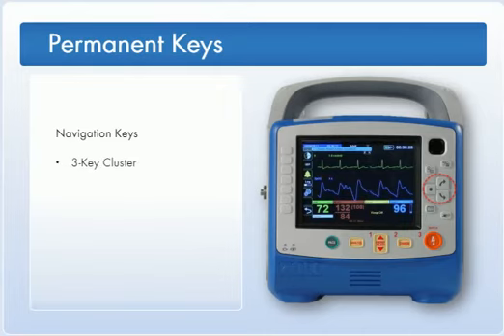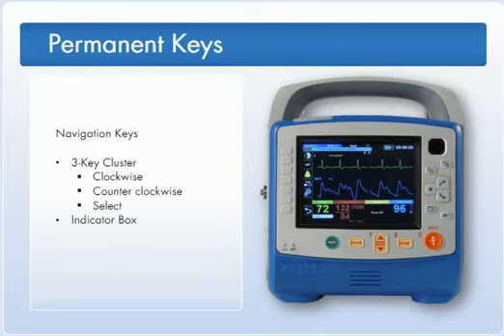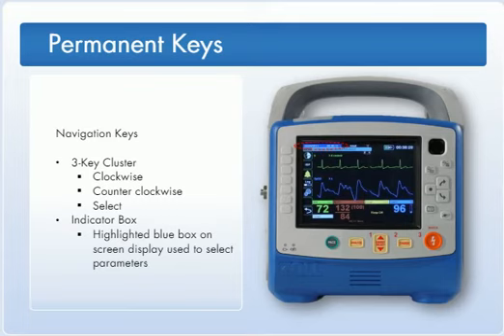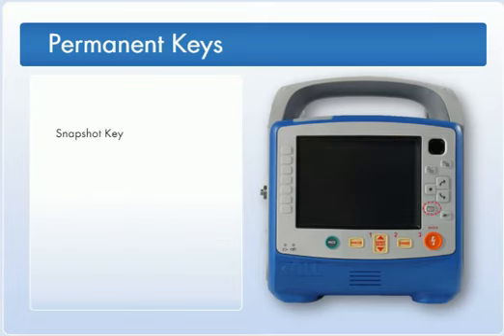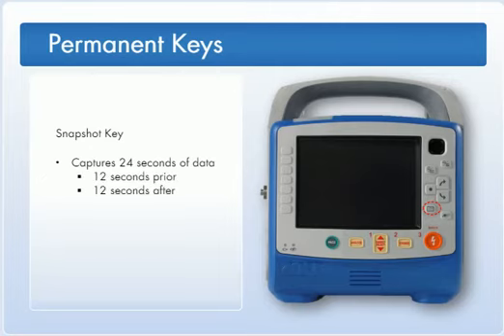The 3-key cluster of navigation keys to the right of the screen, clockwise, counterclockwise, and select, are used to move the indicator box on the screen display and to select options. The indicator box is highlighted blue. Pushing the snapshot key represents the midpoint of a 24-second snapshot. A total of 24 seconds of data is captured, 12 seconds prior and 12 seconds after the key press.